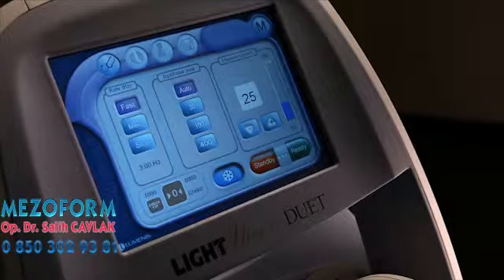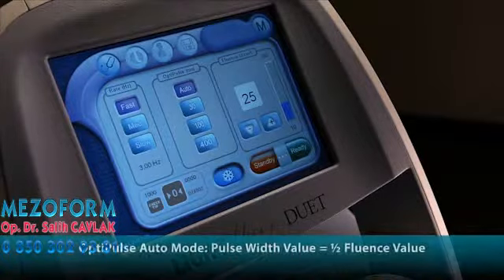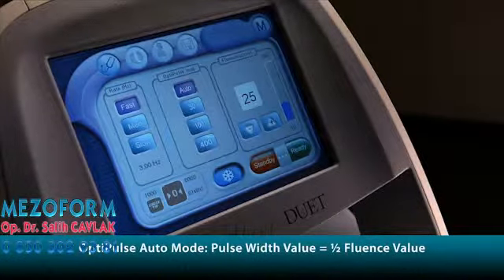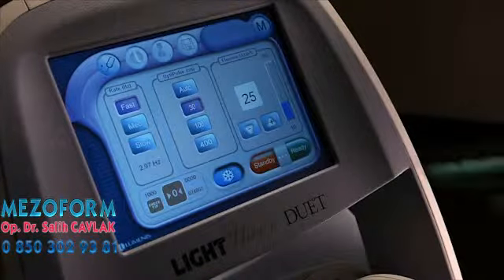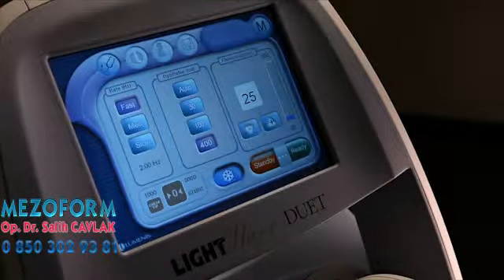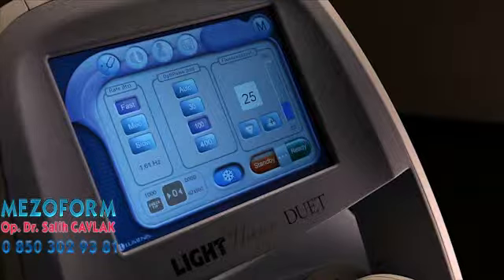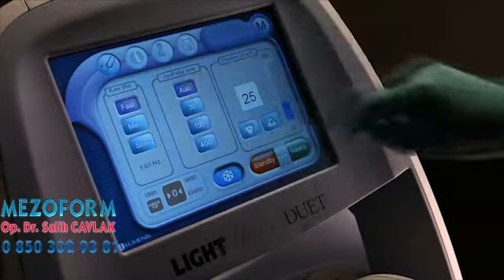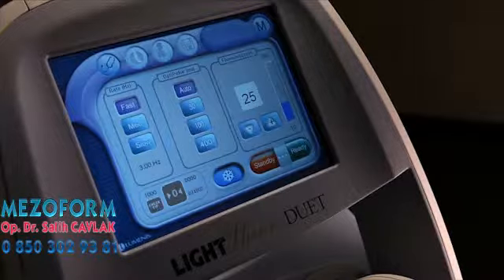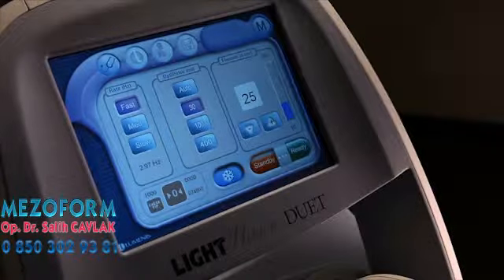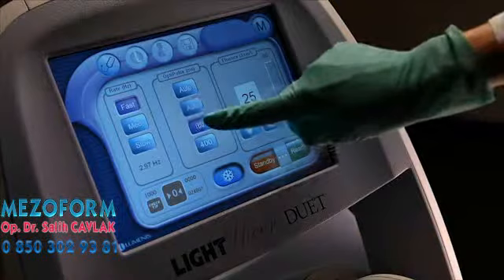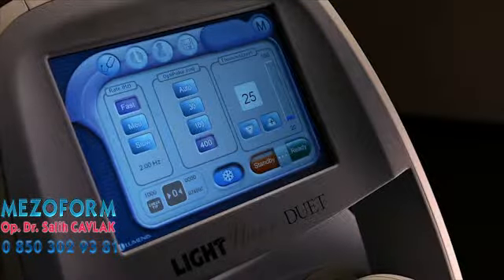In auto mode, the system selects the pulse width allowance at a given fluence. The pulse width is approximately 1/2 the fluence. With 30 millisecond, 100 millisecond, and 400 millisecond, the pulse widths are fixed. Pulse durations are chosen to safely treat specific clinical indications. When using the LightSheer ET handpiece, the auto pulse width is typically used for shallow hair in lighter skin types. 30 millisecond treats deeper and/or dense hair growth and is chosen for slightly darker skin types. 100 millisecond and 400 millisecond are the pulse durations of choice for tanned-skinned and darkest skin types.